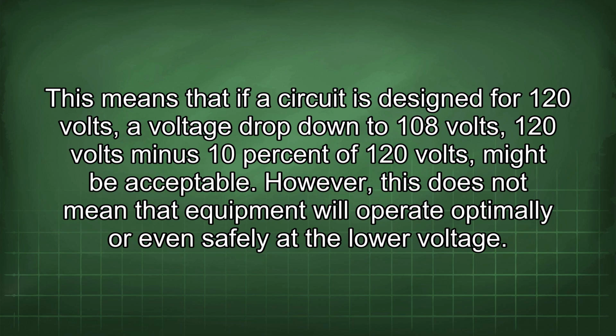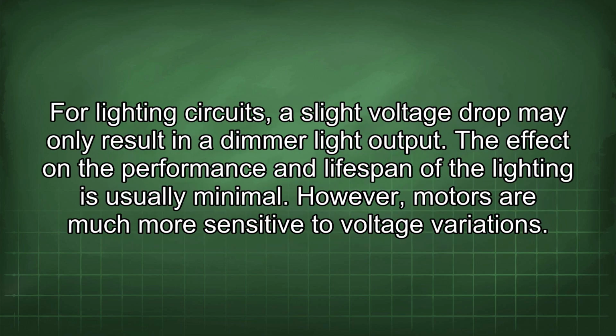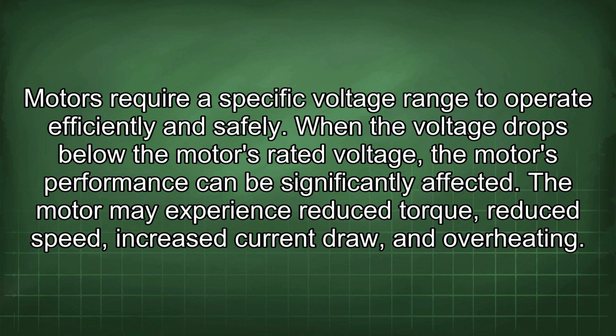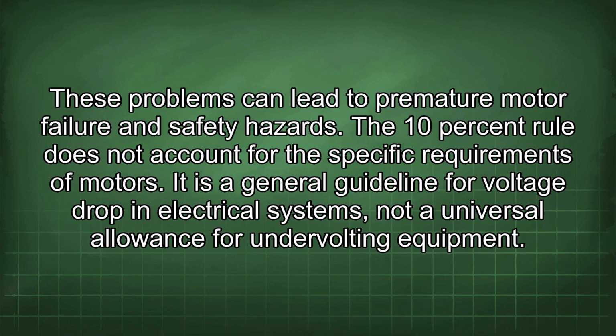However, this does not mean that equipment will operate optimally or even safely at the lower voltage. For lighting circuits, a slight voltage drop may only result in a dimmer light output. The effect on the performance and lifespan of the lighting is usually minimal. However, motors are much more sensitive to voltage variations. Motors require a specific voltage range to operate efficiently and safely. When the voltage drops below the motor's rated voltage, the motor's performance can be significantly affected. The motor may experience reduced torque, reduced speed, increased current draw, and overheating. These problems can lead to premature motor failure and safety hazards.